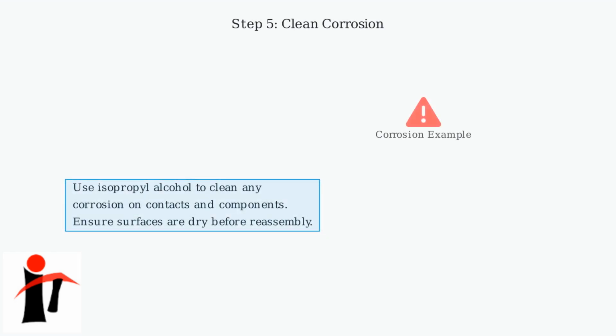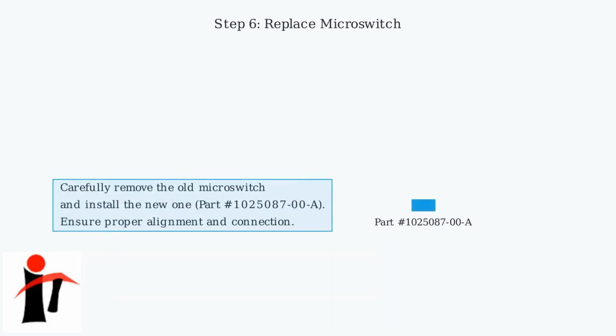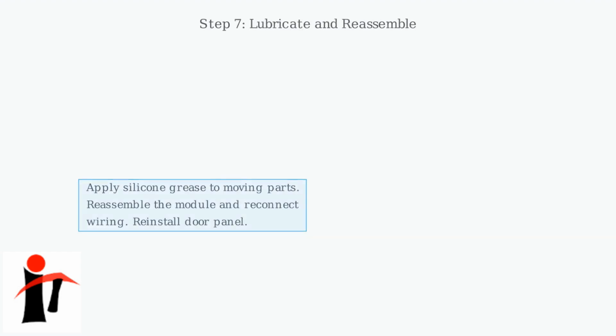Inspect for corrosion on electrical contacts and metal parts. Clean thoroughly with isopropyl alcohol using a soft cloth. Allow components to dry completely before proceeding to avoid short circuits. Remove the faulty microswitch by disconnecting its wires and unclipping it from the module. Install the replacement part number 1025087-00A, ensuring wires are connected correctly and the switch is securely seated. Apply a small amount of silicone grease to any moving mechanical parts to prevent future sticking.